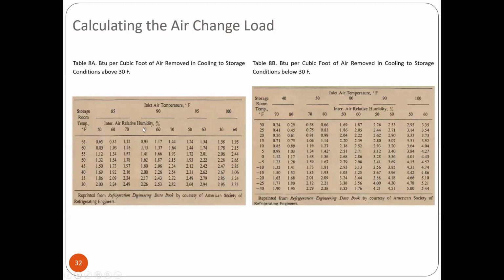So, ito yun. Table 8A is the BTU per cubic foot of air removed in cooling to storage conditions. Cubic feet of air is yung volume ng room. The storage temperature, kukunin mo yung inlet air, Fahrenheit, ano yung humidity. So, ito yung factor mo. Okay? So, this is above 30 Fahrenheit. Ito naman, B is below 30 Fahrenheit.